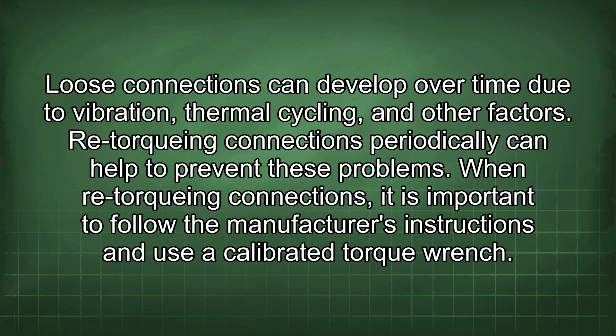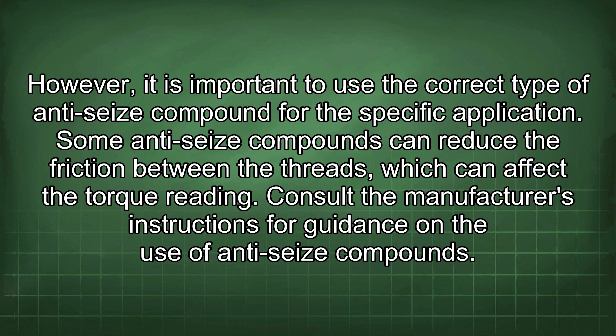The use of anti-seize compounds on threaded connections can help to prevent corrosion and make it easier to torque connections properly. However, it is important to use the correct type of anti-seize compound for the specific application, since some can reduce friction between the threads and affect the torque reading. Consult the manufacturer's instructions for guidance on the use of anti-seize compounds.